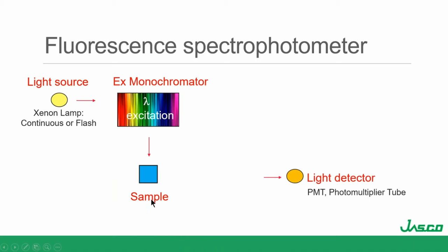Is that a good place to put the detector for fluorescence? No — all of the transmitted excitation light is coming through that way. To our advantage, fluorescence is isotropic — it goes out in all directions. So a better place to put the detector is at 90 degrees, because that's going to minimize any of that scattered excitation light.